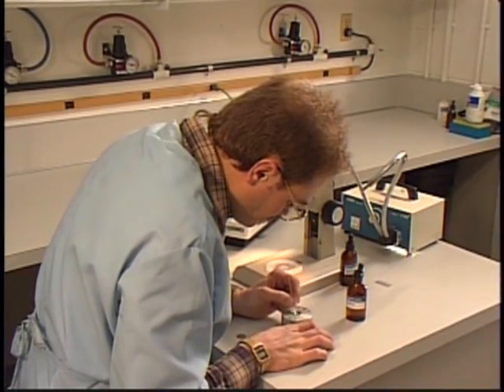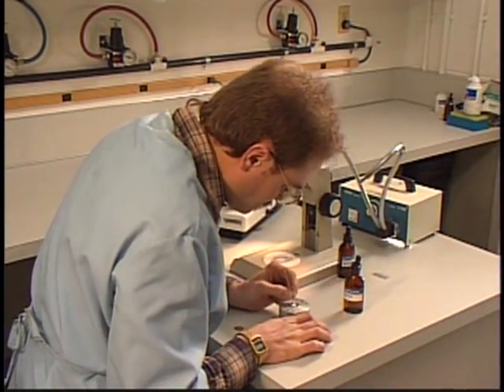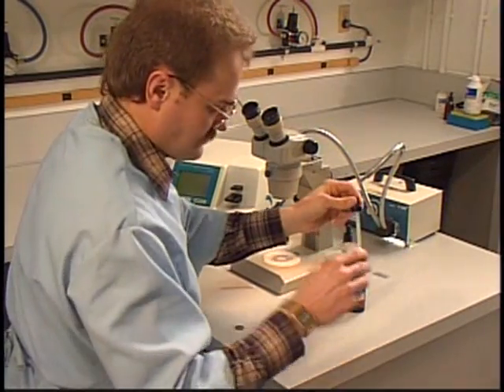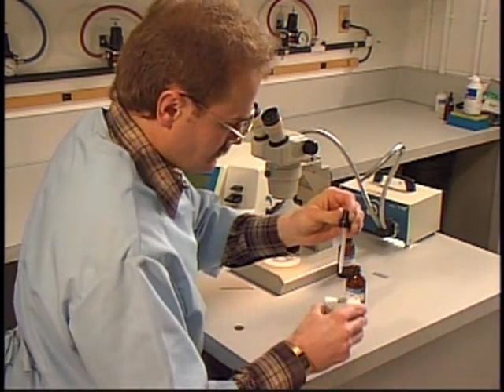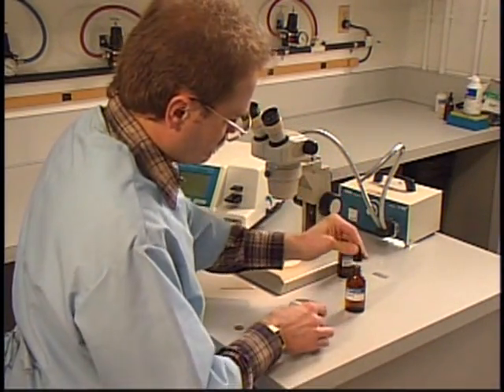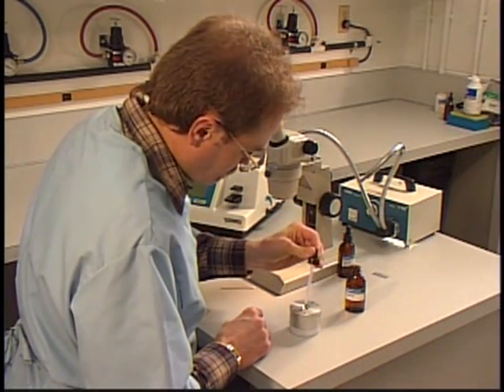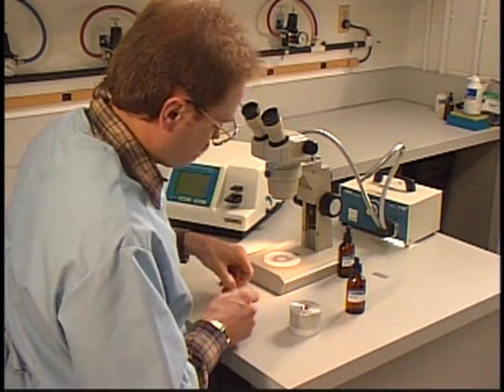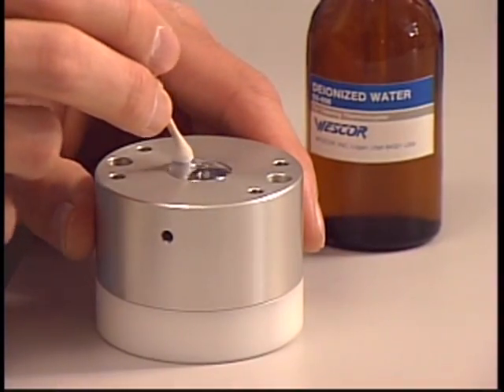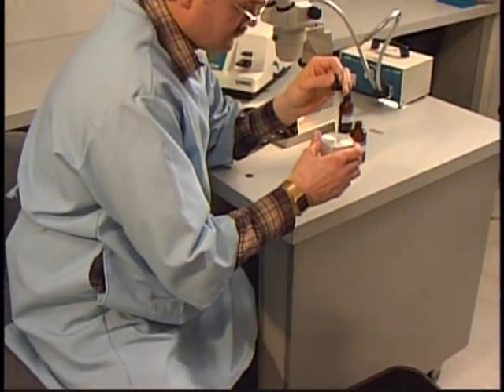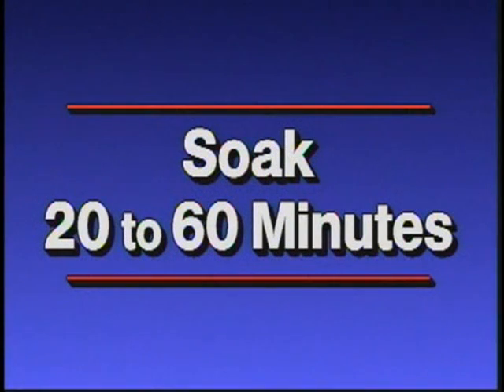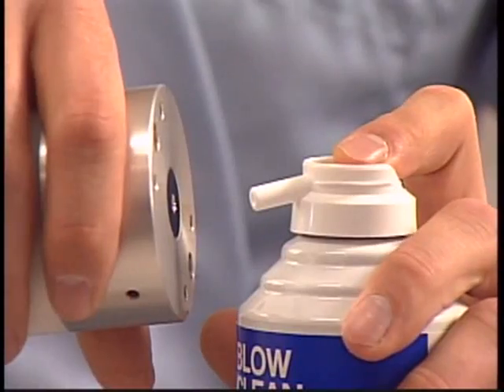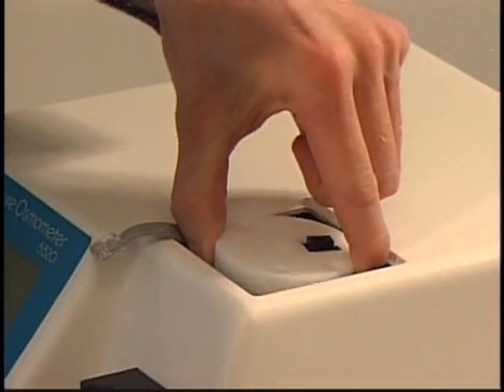Now take swab number 2 and swab around the thermocouple. Shake off the cleaning solution and immediately rinse with DI water 2 or 3 times. A few more drops of deionized water and it's time for swab number 3. A round of rinse aerobics. Then a soak in DI water for 20 minutes or even an hour while you're having lunch. Enough time to get rested up for another exercise session, a blow dry, and back into the machine.